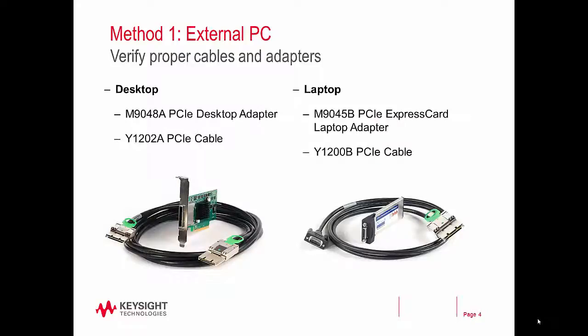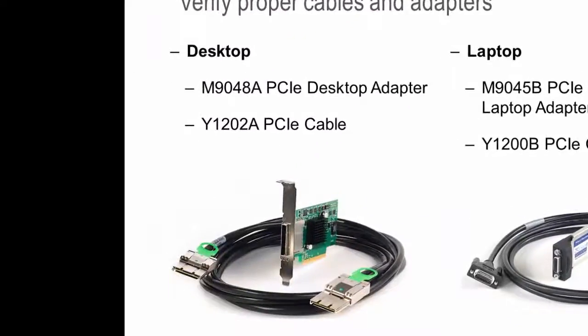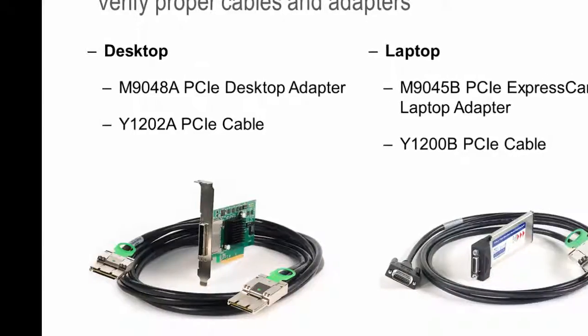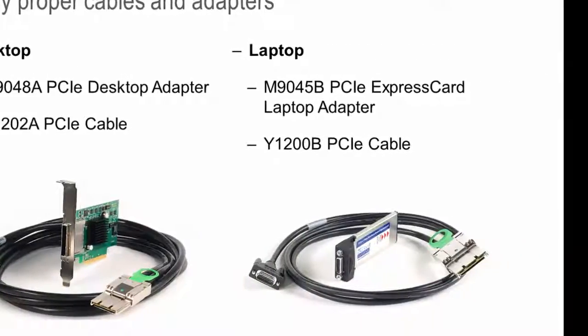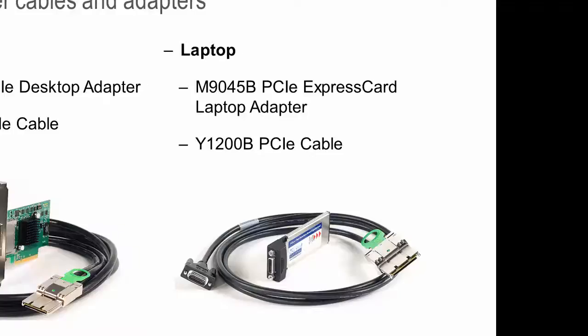When using an external PC, also verify that you have the proper adapters and cables. These vary depending on if you are using a desktop or a laptop. For a desktop, you need the M9048A PCIe desktop adapter and the Y1202A PCIe cable. For a laptop, you need the M9045B PCIe express card laptop adapter and the Y1200B PCIe cable.